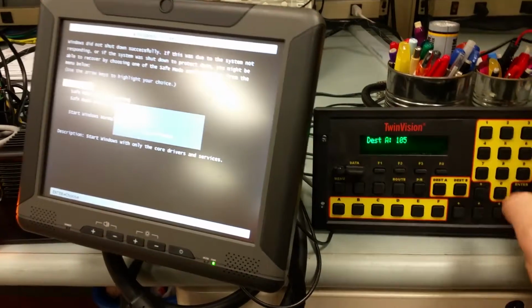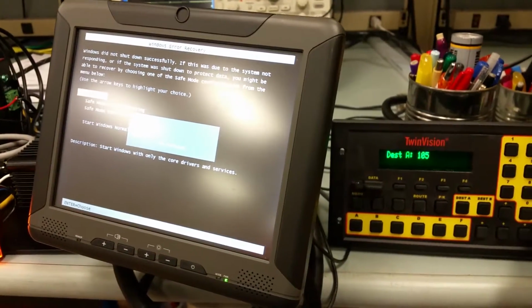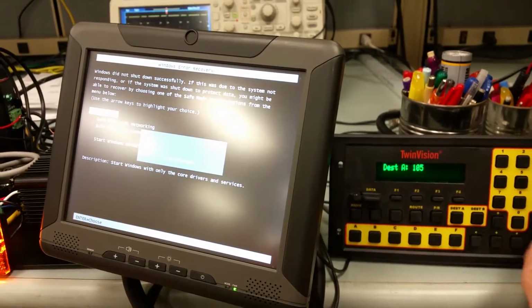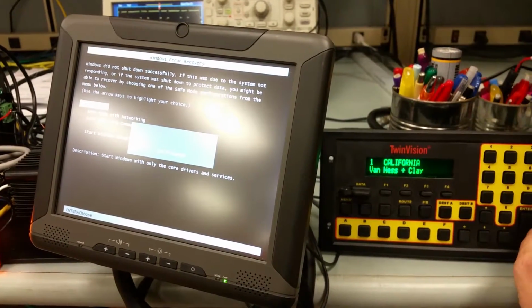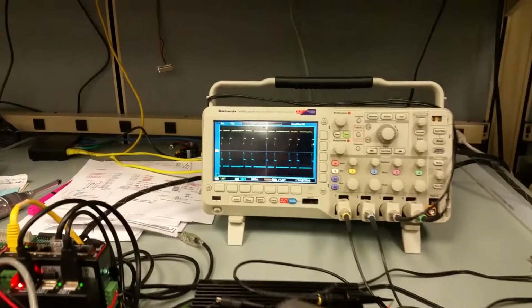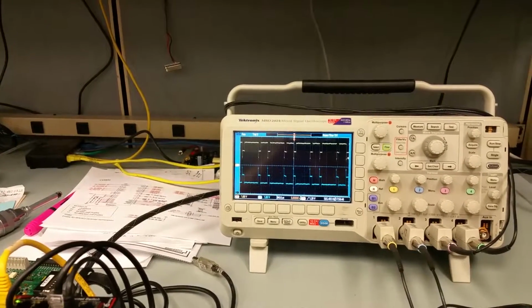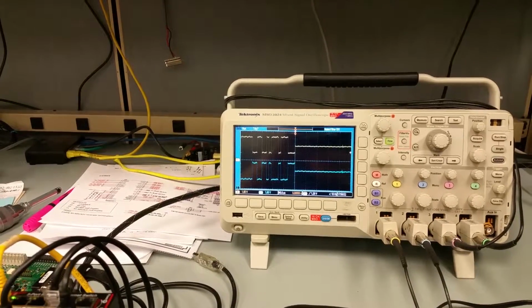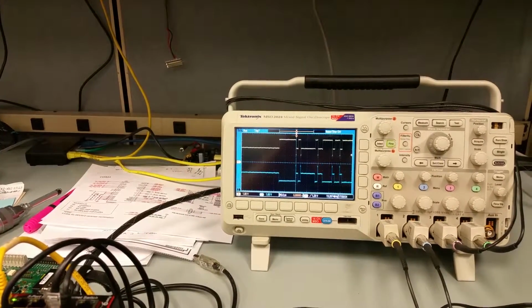And what you'll notice now is when I hit the enter key that communications has resumed and is performing, the OCU is performing as designed. And it's also further demonstrated by that the 485 signals are at proper amplitude and spacing.